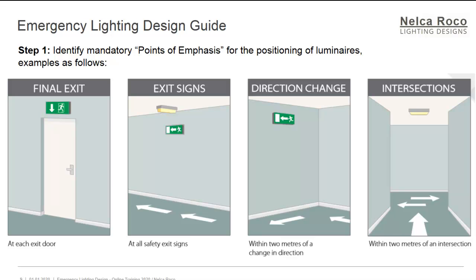Emergency lighting design guide: Step 1 is to identify the mandatory points of emphasis for the positioning of luminaires. Examples include the final exit — for example, the exit door and exit signs where you need to go. For all safety exit signs you need to identify those points, and also the direction of change — for example, if there is a corner, you need to identify that and put an exit sign for that area.